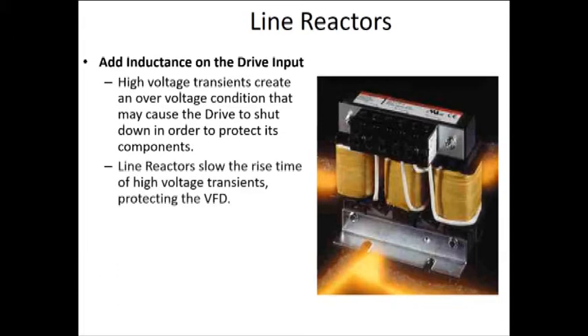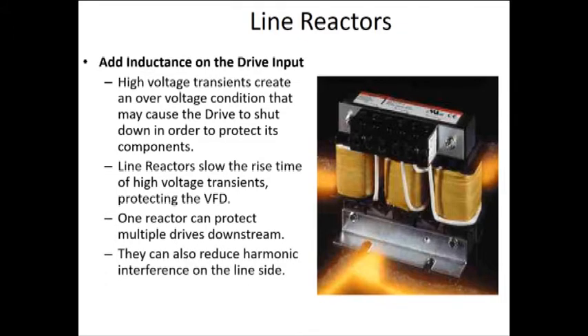Compared to the drives they protect, they are relatively inexpensive, and one of the great things about a reactor is that one of them can protect several drives in an installation. Line reactors can also help reduce harmonics in an electrical system that are caused by a VFD's irregular sine wave. And if you put them on the output side, they can help protect motors from damage caused by reflected wave spikes over long cable runs.